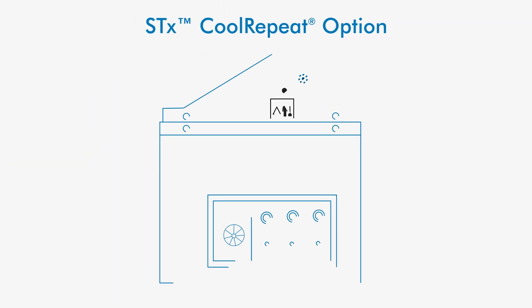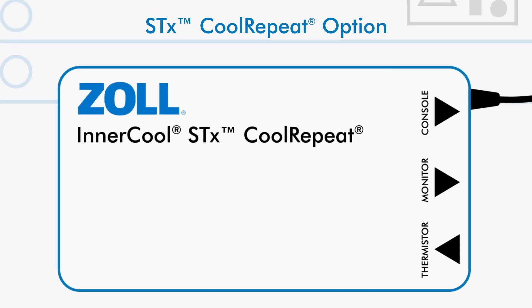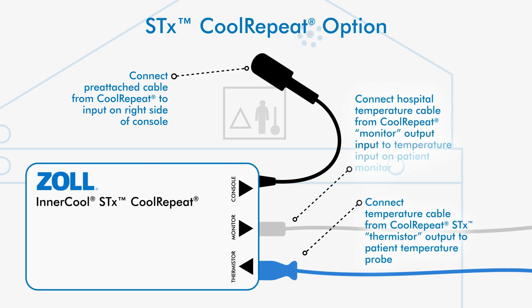Connect the patient core temperature probe to the temperature cable adapter and insert the temperature cable adapter into the Zoll STX console. If using cool repeat, connect the cool repeat to the console and insert the temperature cable adapter into the thermistor port on the cool repeat.